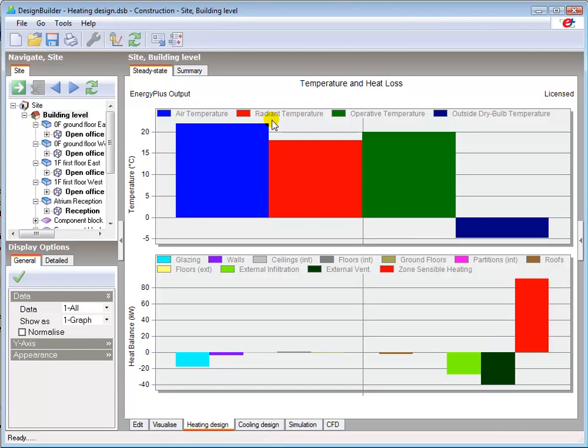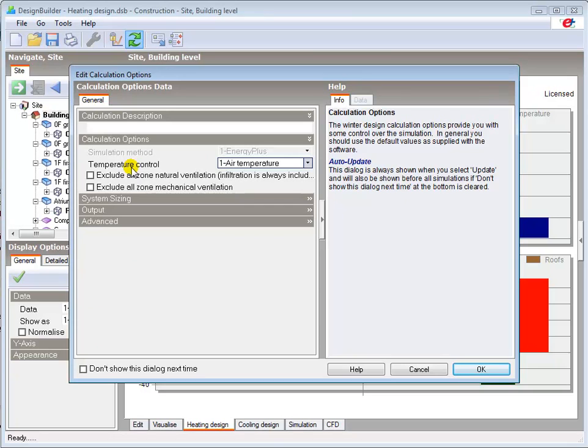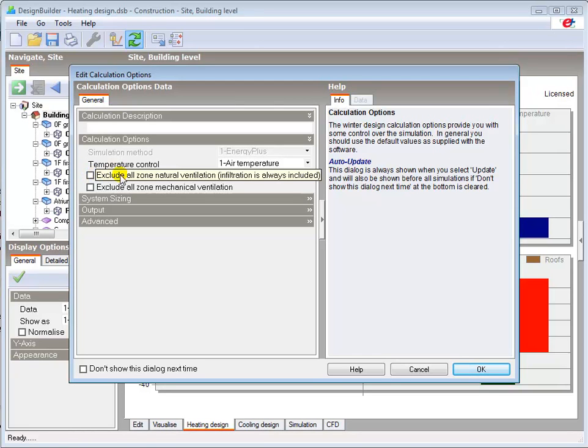If your model includes natural or mechanical ventilation systems and their associated controls you can specify whether or not you want to exclude these from the calculation. They are of course included by default as they can significantly increase the heating load in a building. Note that this comment regarding infiltration always being included is only true when infiltration is switched on in the construction tab.